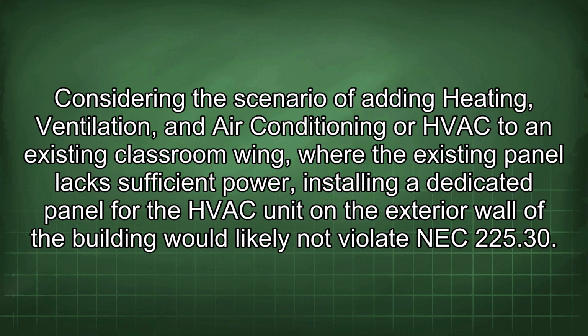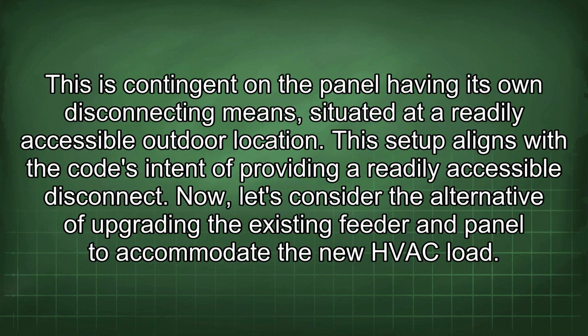Considering the scenario of adding heating, ventilation, and air conditioning, or HVAC, to an existing classroom wing, where the existing panel lacks sufficient power, installing a dedicated panel for the HVAC unit on the exterior wall of the building would likely not violate NEC 225.30. This is contingent on the panel having its own disconnecting means situated at a readily accessible outdoor location. This setup aligns with the code's intent of providing a readily accessible disconnect.